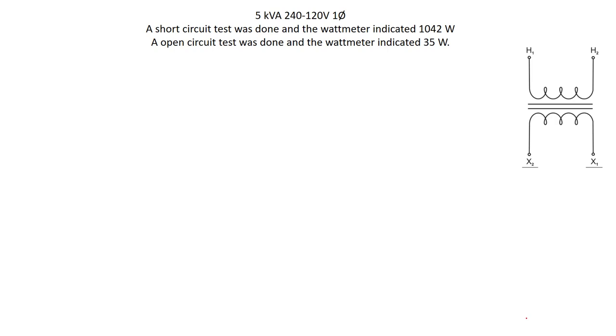We have a 5kVA 240 to 120 single phase transformer. We did a short circuit test on it, and during the short circuit test the watt meter indicated 1042 watts. In the short circuit test, we hardly had any voltage applied to make rated current flow through the secondary, and the watt meter on the primary read the copper losses — both primary and secondary combined. We also did an open circuit test and the watt meter indicated 35 watts. On the open circuit test, we put rated voltage on it with no load on the secondary, and that 35 watts is the core losses.